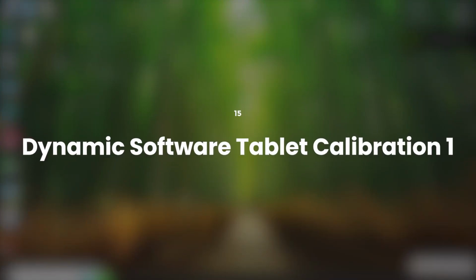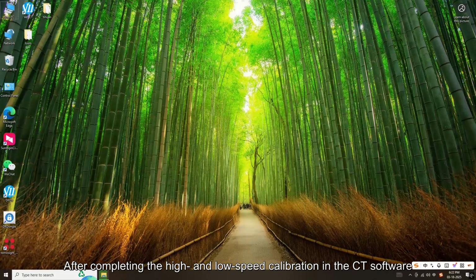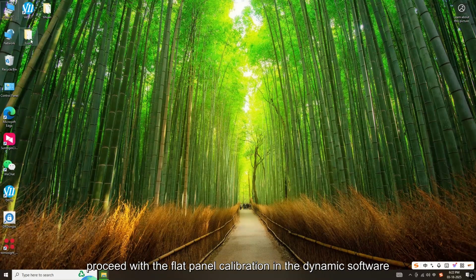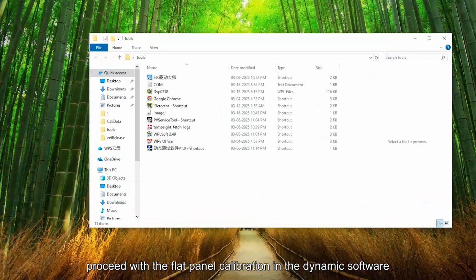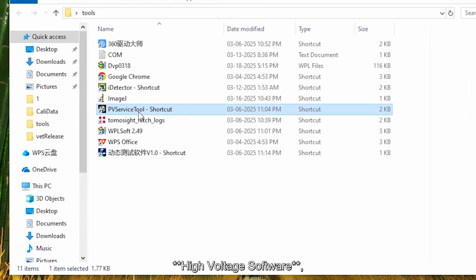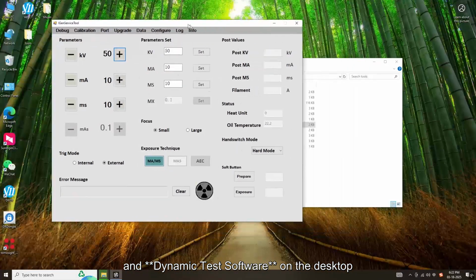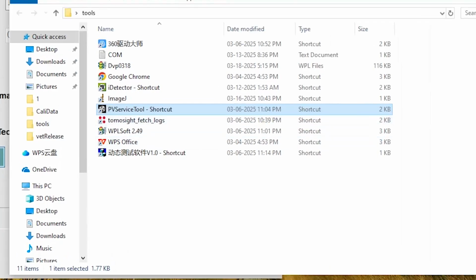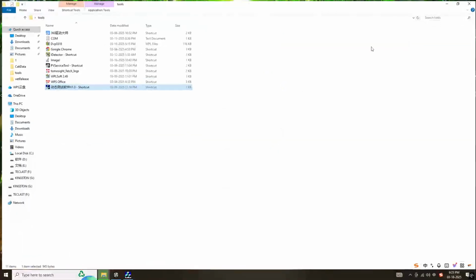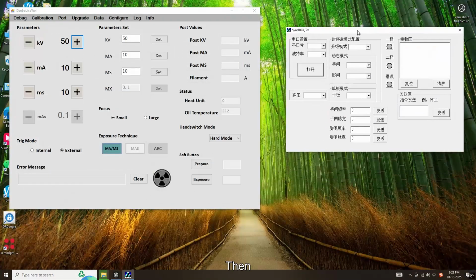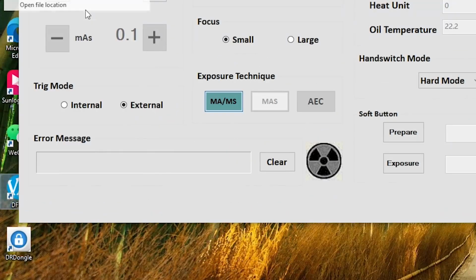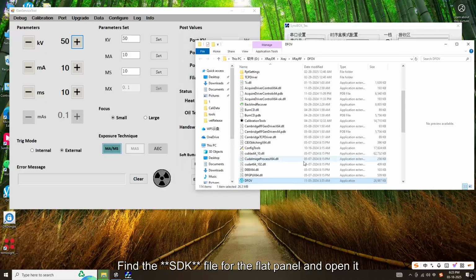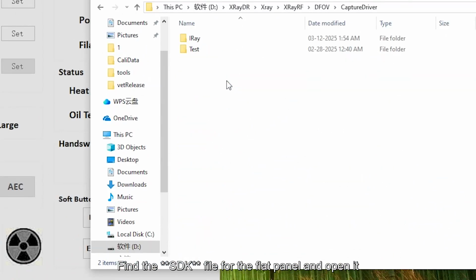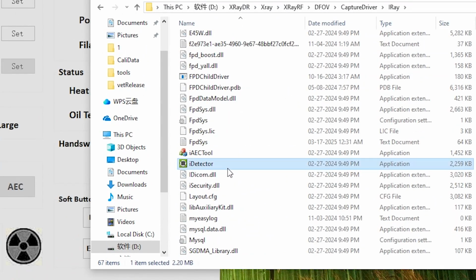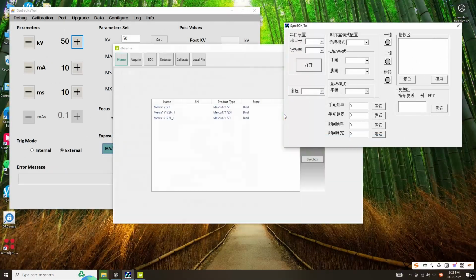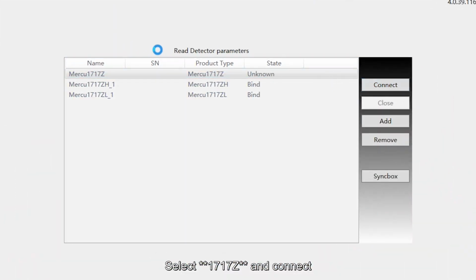15. Dynamic Software Tablet Calibration 1. After completing the high and low-speed calibration in the CT software, proceed with the flat panel calibration in the dynamic software. First, open the tool, High Voltage Software and Dynamic Test Software on the desktop. Then, open the DR file location. Find the SDK file for the flat panel and open it. Select 1717Z and connect.